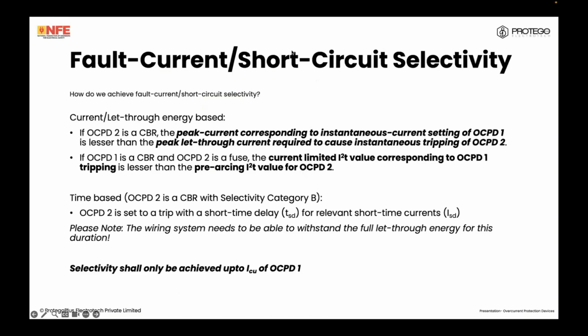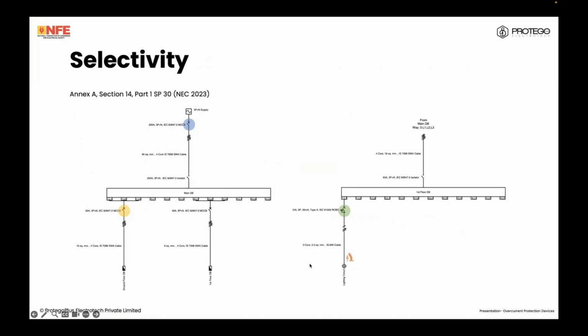So, how do we determine whether there is selectivity? If OCPD2 is a circuit breaker, we have to compare the peak current corresponding to the instantaneous current setting of OCPD1, and we have to make sure this is lesser than the peak let-through current required to cause instantaneous tripping of OCPD2. So we'll go back to the diagram here. When there is a fault here, we need to ensure that the peak current on the first half cycle is not enough to trigger a trip here. Plain and simple. We'll get these values from the manufacturer. I'll show you an example as well.